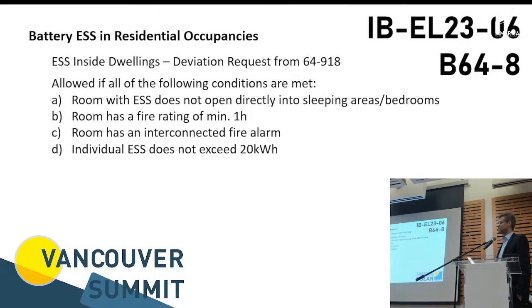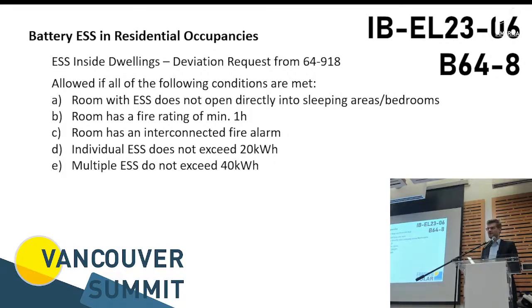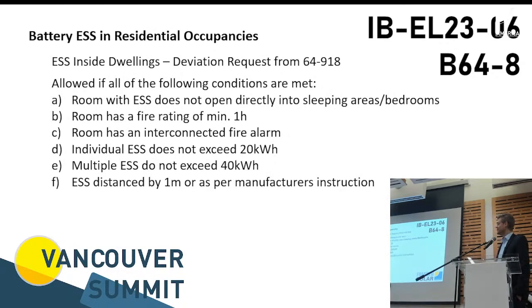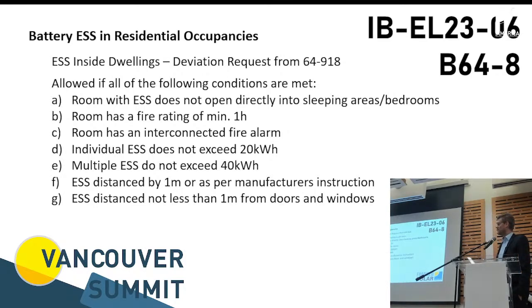And you have limitations: an individual certified system in its cabinet cannot exceed 20 kilowatt hours. And if you have multiple of them, let's say a larger customer wants more capacity, then you have a 20 kilowatt hour increment, a certain separation distance, and another 20 kilowatt hour increment, up to a total of 40 kilowatt hours for the entire building. Or if the manufacturer has done the fire propagation testing with the cabinets side by side, so not the 1 meter in between, then you can line them up to whatever the manufacturer's specifications are. And for Ontario specifically, that doesn't apply to BC, you have to have a minimum distance to egress windows or doors of minimum 1 meter.